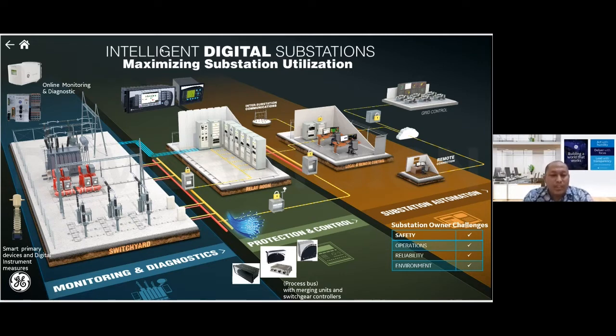And then also in this digital substation, we can apply online monitoring and diagnostics. For example, we can use online monitoring diagnostics on the transformer side, and we can also install monitoring diagnostics in the circuit breaker equipment. By having this kind of monitoring and diagnostic equipment, we can pull much data from the equipment that we have on site. With this data, operators and engineers on site can analyze when the equipment needs to be under maintenance and when components need to be replaced, something like that.